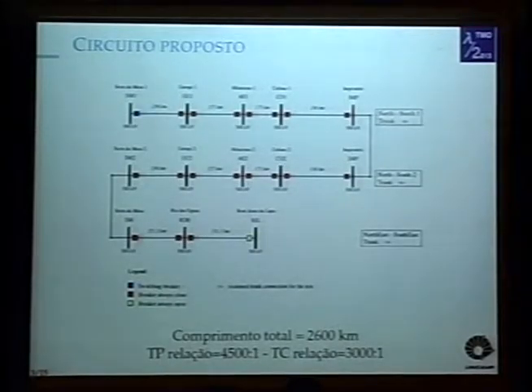We call it Serra da Mesa 1 here. And it is connected with the 0321 relay that we have in the laboratory. So all the other circuit breakers are always closed. We have in this line of 2,600 kilometers, the power transformer ratio is 4,500 to 1, and the current transformer ratio is 3,000 to 1.